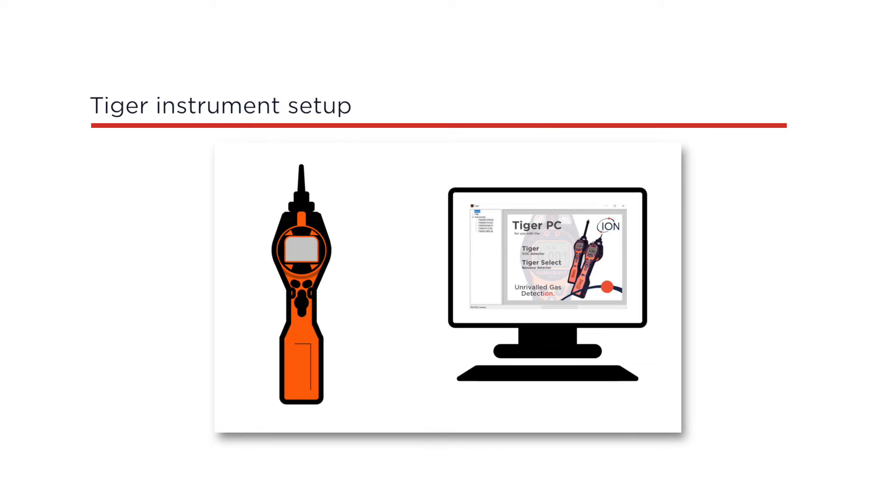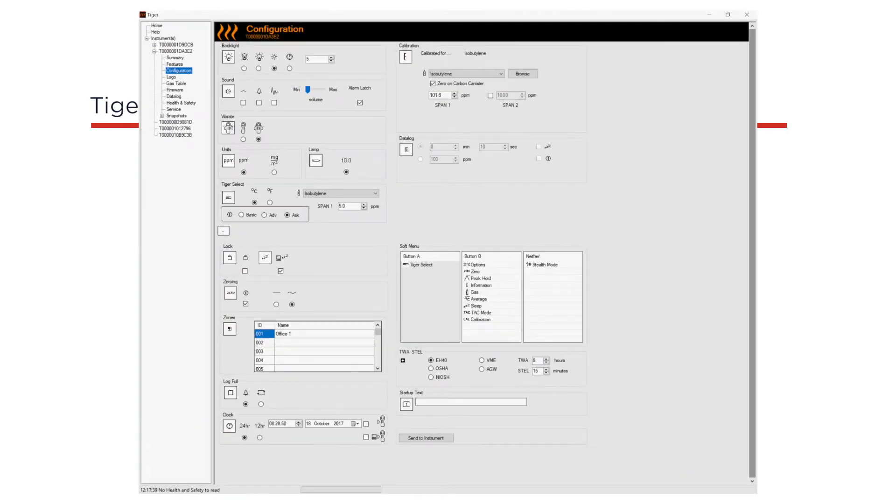Open the TIGER software and connect your TIGER instrument via USB. Go to the configuration page. In the calibration section, set span 1 to the gas level on the gas bottle. Select the zero on carbon canister option and ensure span 2 is unselected. Now press the send to instrument button.